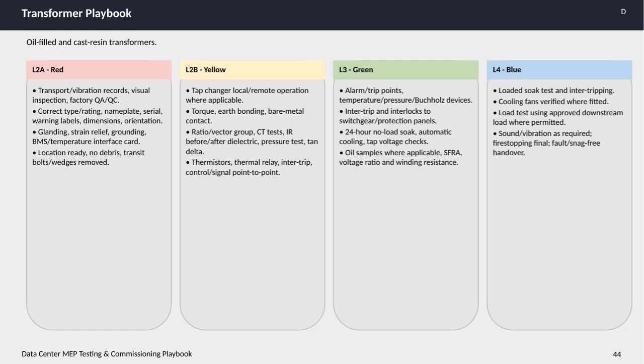Key alarm and trip points related to temperature, pressure, and Buchholz devices are verified. Integration with switchgear and protection panels is confirmed through inter-trip and interlock checks. The transformer undergoes a 24-hour no-load soak, with automatic cooling systems and tap voltage checks performed during this period. Where applicable, oil samples are taken for analysis, alongside sweep frequency response analysis, voltage ratio measurements, and winding resistance checks.